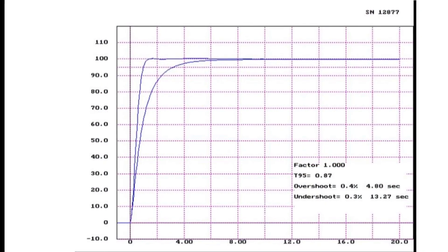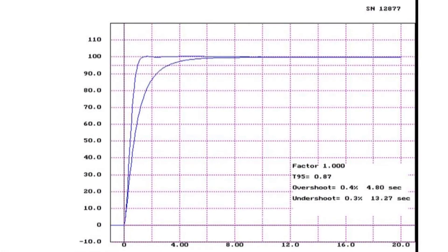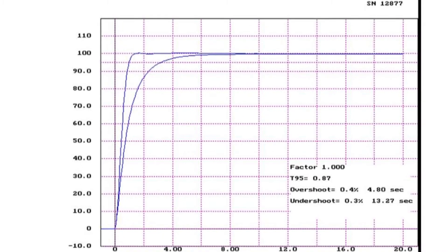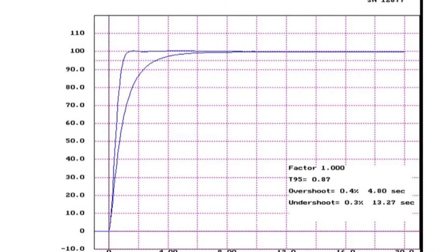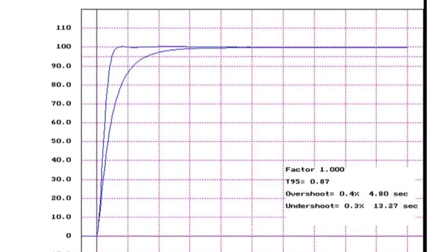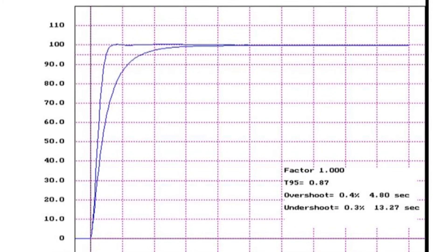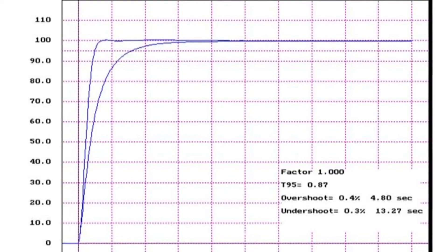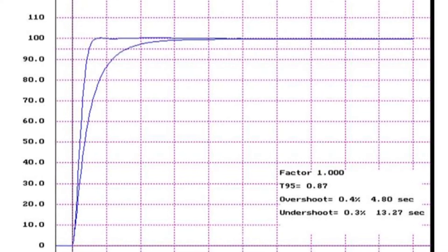A speedup algorithm is used to speed up the response time of the sensor, giving a reading after approximately one to three seconds instead of the longer physical response time, which in some cases might be as high as 10 seconds. This speedup is set during calibration and stored as a mathematical function inside the sensor's EEPROM, represented by yet another factor.